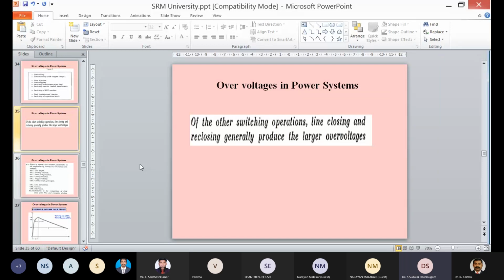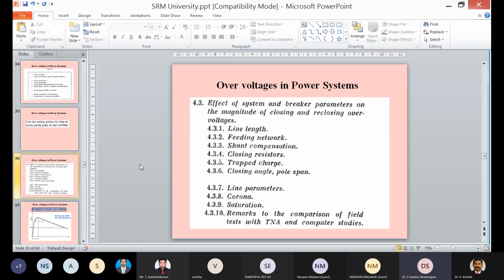I repeat, during the closing and opening of your circuit breaker, the switching transient effect will be very predominant, and especially when the system voltage is more than 245 kV, the switching transient becomes a significant influence, increasing by leaps and bounds. That's why after 245 kV, we will test the equipment for switching impulse voltage and lightning impulse voltage.